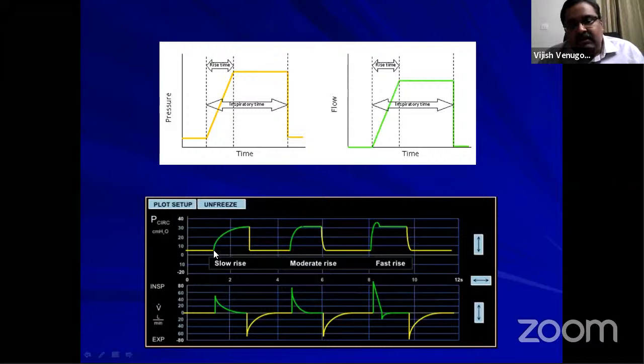If you keep this rise time at around 1 second, there is a very slow rise, and you can see in the picture below there is a slow rise. And here you can see this is a moderate rise. And the third one is the fast rise, where you can see there is a peaking of the curve. So the flow or the limit is reached very fast. Ideally we keep this around 0.2 seconds, so around 200 milliseconds is what the rise time is usually set at. But in patients with air hunger, you might have to keep an even smaller rise time so that the patient's air hunger is satisfied. So that is regarding rise time.